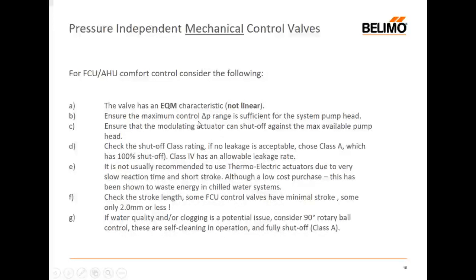I should ensure that the control range of the valve is sufficient for the system pump head. Earlier we saw a valve at between 16 and 600 kPa, so if I've got a 5-bar pump, no problem. If I've got a 7-bar pump, I might have to think again. Ensuring that the modulating actuator can actually close against the available pump head is important, because although we're maintaining a relatively low delta P while the valve is open, the minute the valve closes, it does see the available pressure. The maximum available pressure could be quite high, so we should consider an actuator able to close. We should think about maybe the class rating, the shutoff class rating. If no leakage is acceptable, we should choose class A.